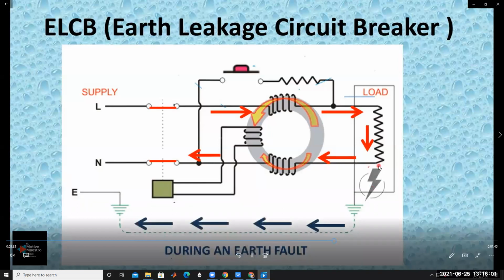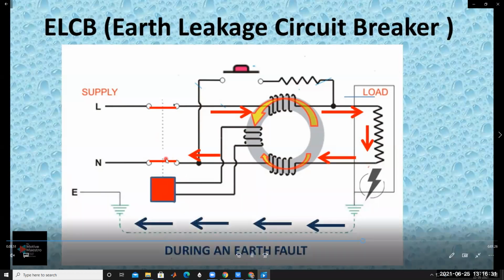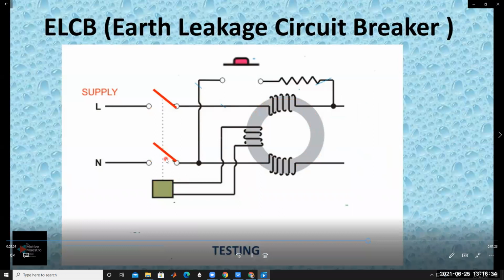So this earth fault current is flowing to the earth wire under faulty condition, and this way the earth leakage circuit breaker is working. During fault conditions it operates in this way; the sensing coil is operating in this manner. Because of this, the net flux is not equal to 0. That's why the sensing coil senses the flux, and then the tripping coil opens the contacts. That means the supply is disconnected, which isolates the faulty section from the healthy section, and it also protects human beings from earth leakage.